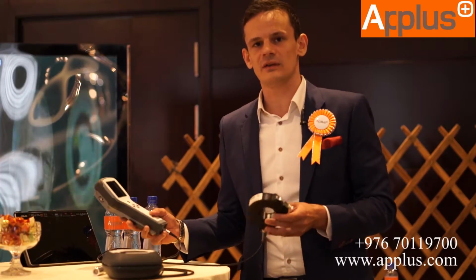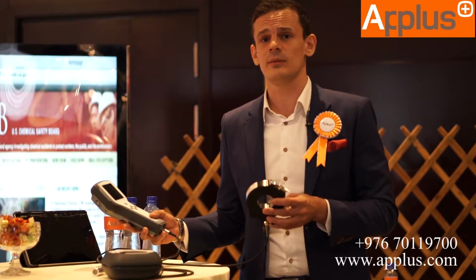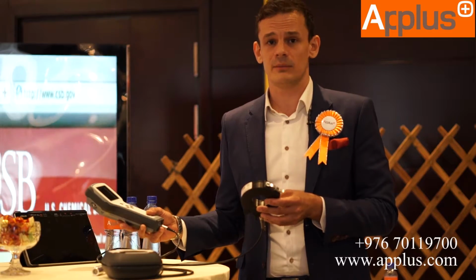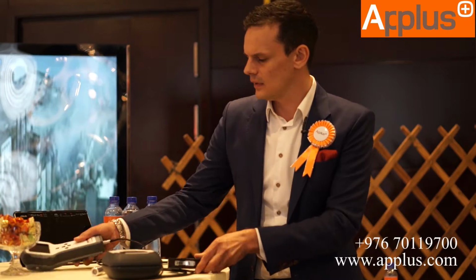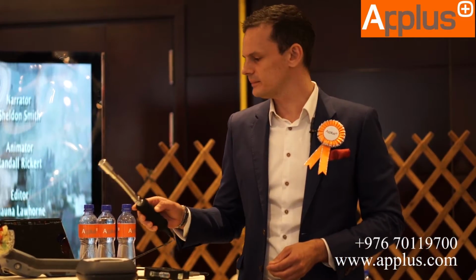Using the accessories, we can test any breakdown in insulation in cables to detect faults before they cause a catastrophic failure. We're able to use another accessory outside for switchgear, switch rooms and high voltage power networks. The reporting is easy, straightforward and simple to carry out.